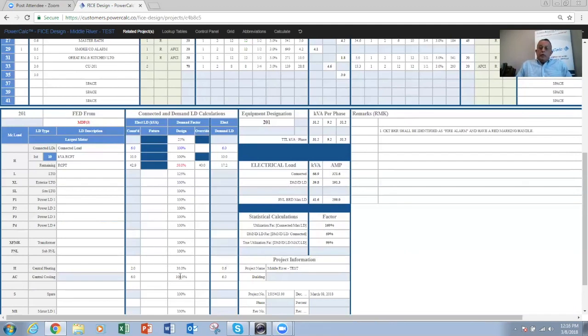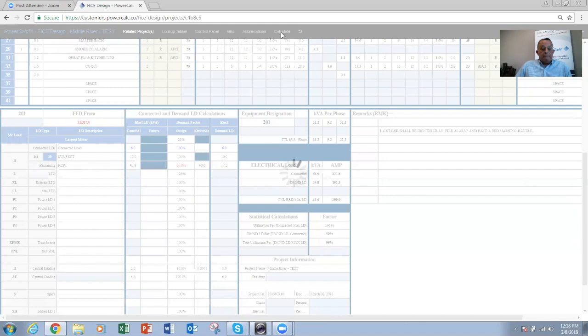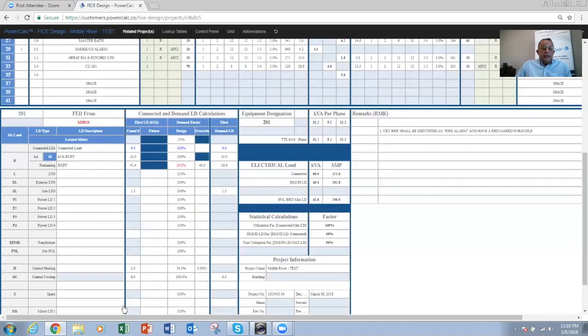And the reason I set it up that way is just because during the heating cycle, you have the heater and the fan running being used during the cooling cycle. So there's kind of an overlap between the heating and cooling cycle for the same load. Now you can go ahead and adjust that if you want to. That was my preference, the 30%. If you don't, type 0001 and enter, and then calculate, it will take it out of your calculations. Okay, so you see here now the two connected. When we demanded at 0, it took out the demand load completely off the connected load.